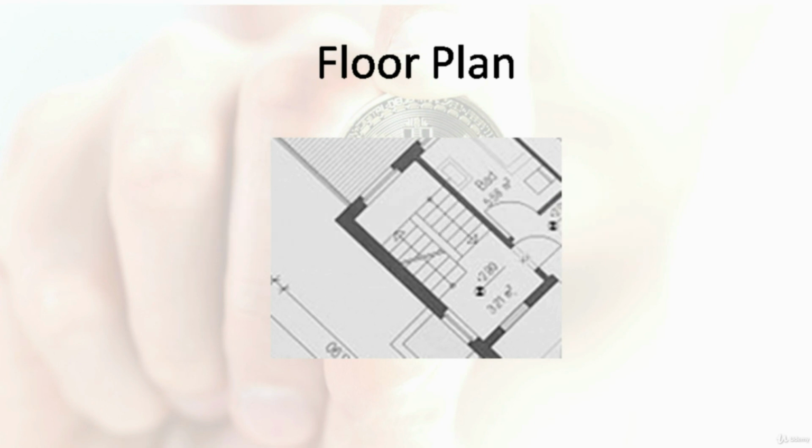A map of the facility is one of the most important records to provide in a crypto mining farm. A map or floor plan at the very least should display clearances, cabinet positions, major equipment placement, and the mining farm's numbering scheme. This knowledge is valuable when allocating space for new mining rigs and important for planning future expansions.